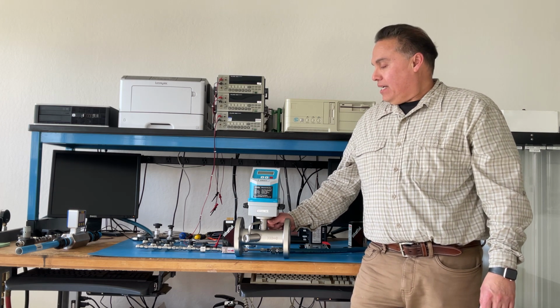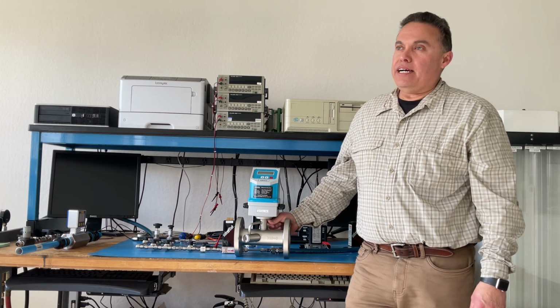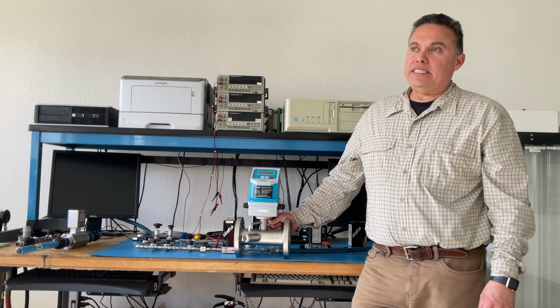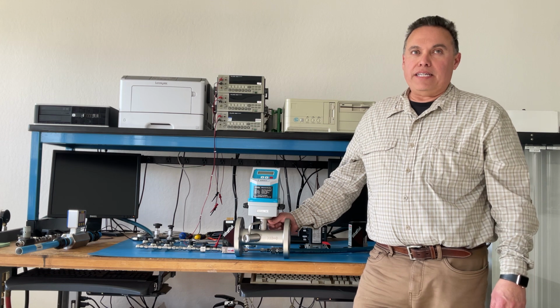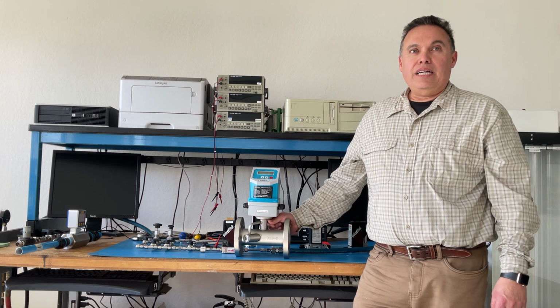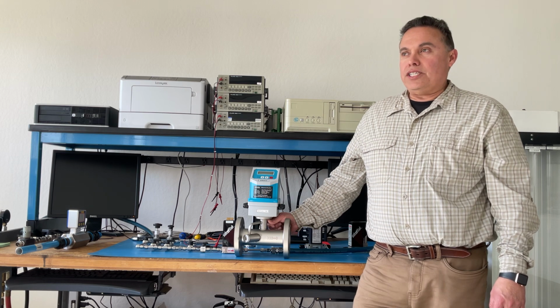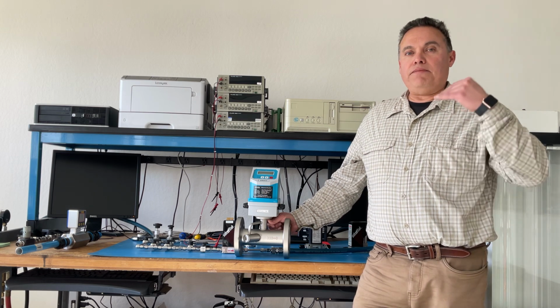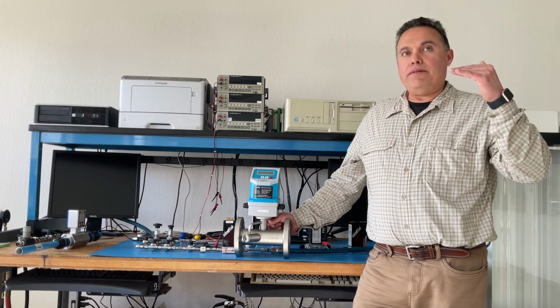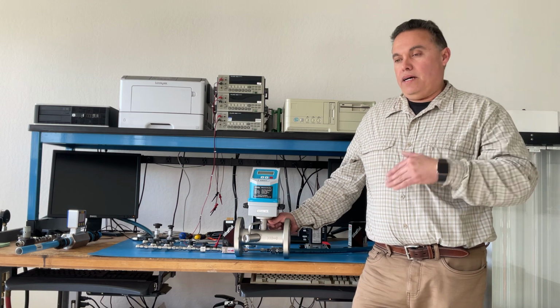Very good. Yeah. So this meter has, for fluids, the highest turn down ratio of any technology. You'll get a 250 to 1 turn down on this meter. By turn down ratio, what do you mean? Essentially, you take the maximum flow rate that the meter could read divided by the minimum flow rate that the meter could read.